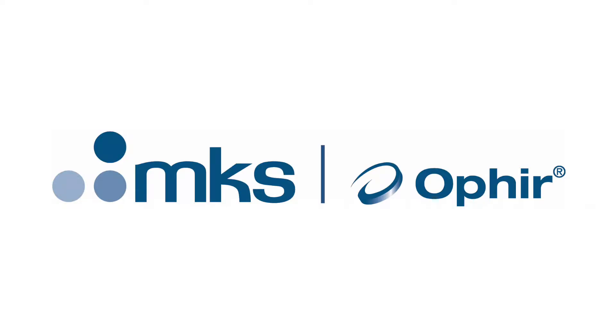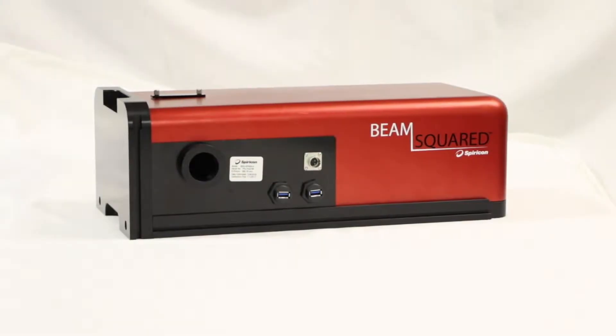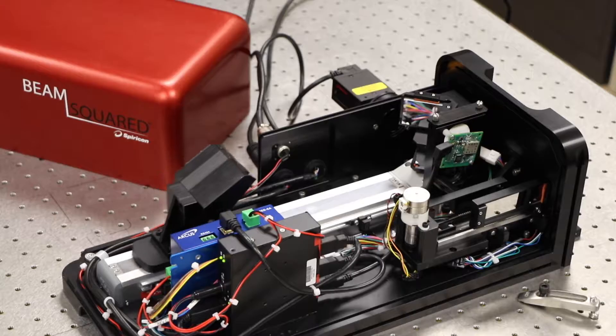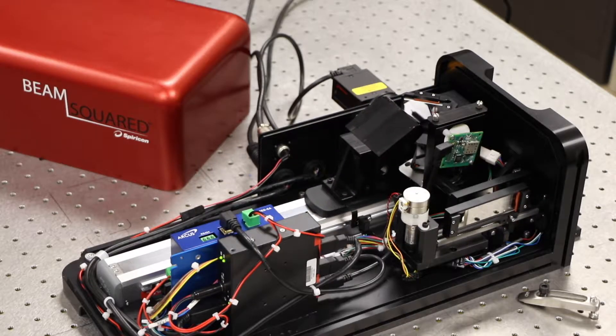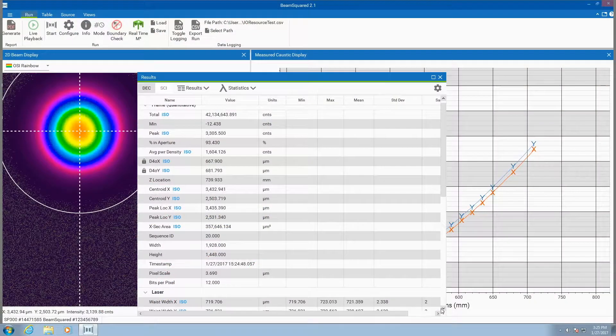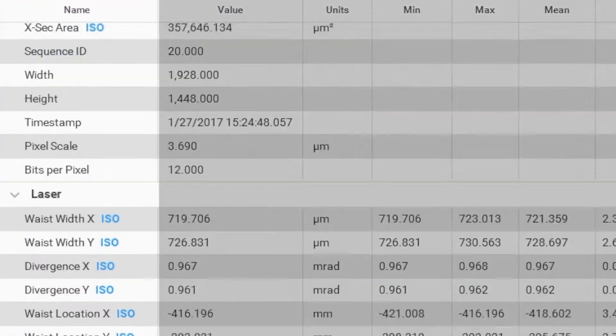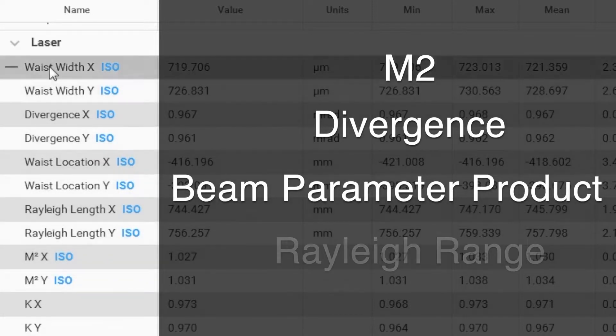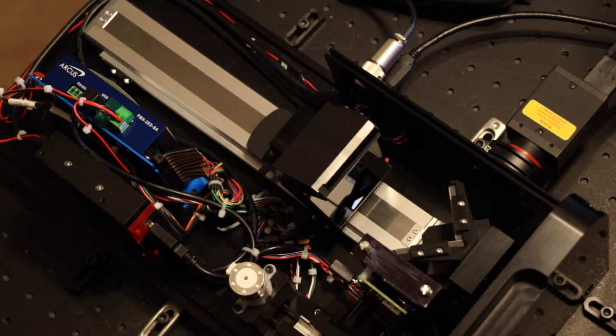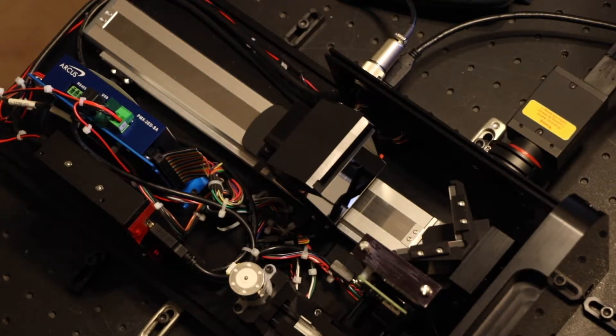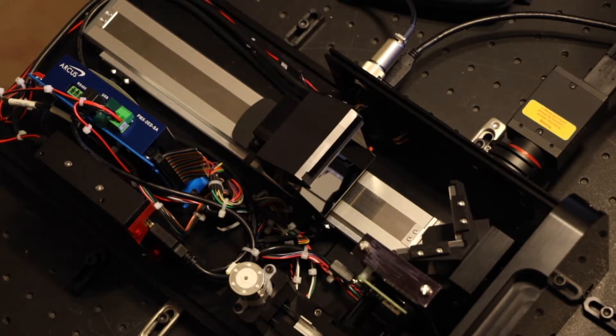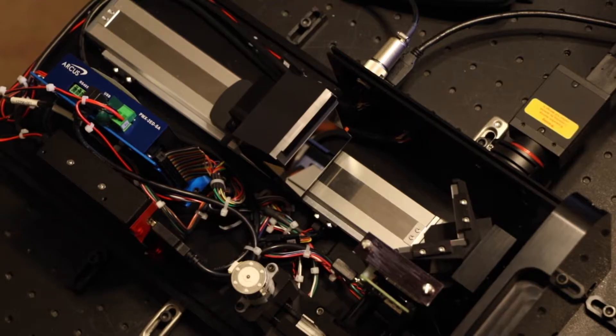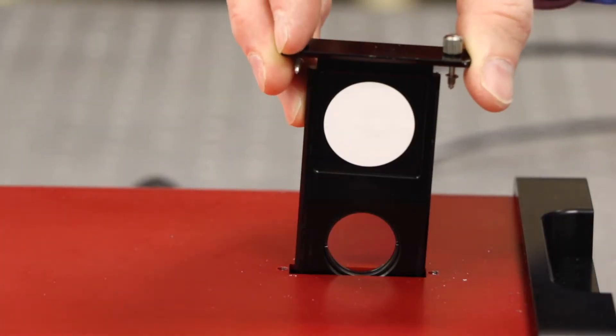Ophir introduces an exciting new feature for the Automated Beam Squared Laser Beam Propagation Measurement System. The Ophir Beam Squared automatically scans your laser beam to measure important propagation characteristics, including M-squared, divergence, beam parameter product, and Rayleigh range. It uses a variable length beam path to measure the beam dimensions at multiple locations along the focused region, or caustic, that is created by the supplied focusing lens.